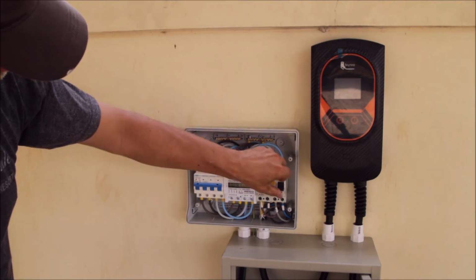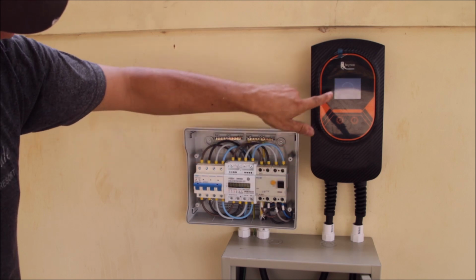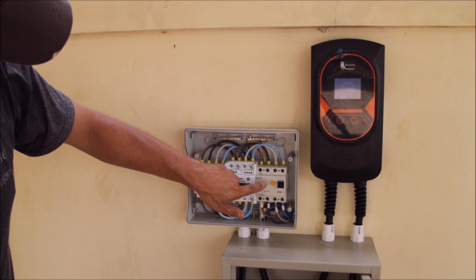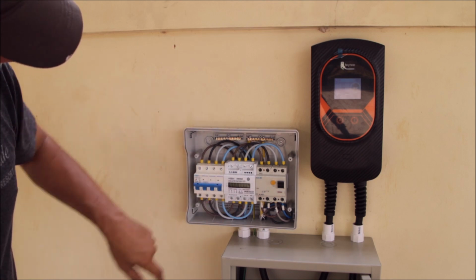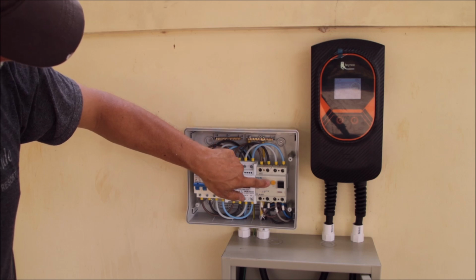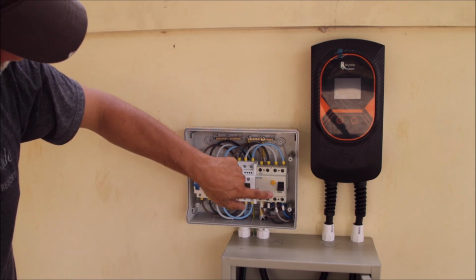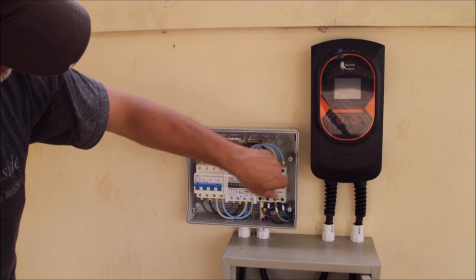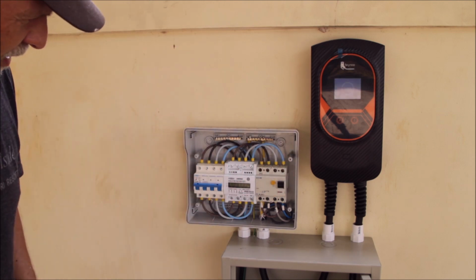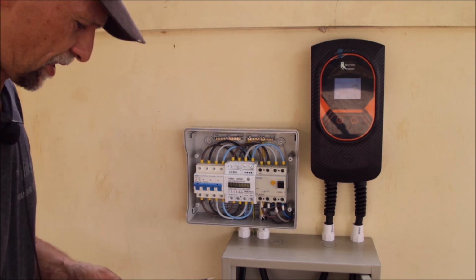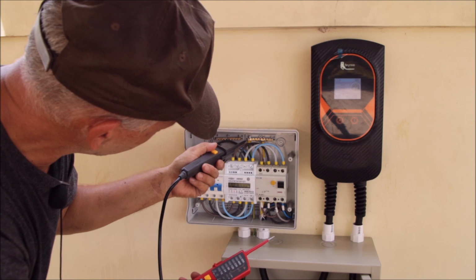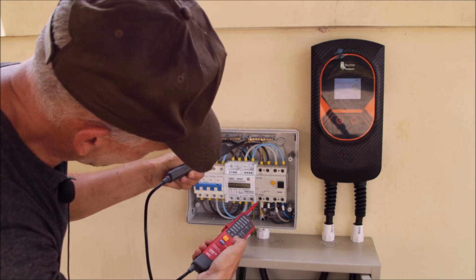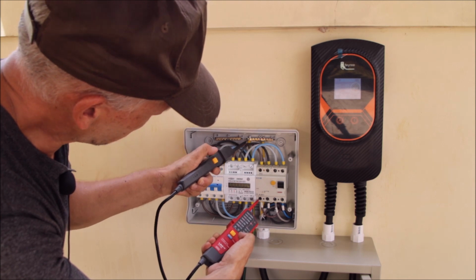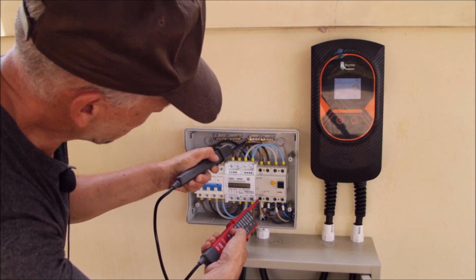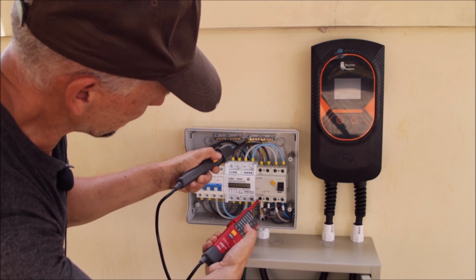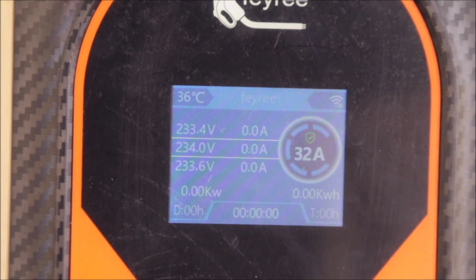Okay, now we only have the RCD here. Put this one up, and it already gives us power to the wall box. But let's test it first. This is rather old one. I brought it from Austria, probably already 20 years old. The test is working. This test is of course only telling us the internal test is successful, but we can test it also externally. What I have to do is I can take here ground and go to one phase, so we see 230 volts, and if I am pressing now these 2 buttons, we must actually activate the RCD, and it's perfectly working.